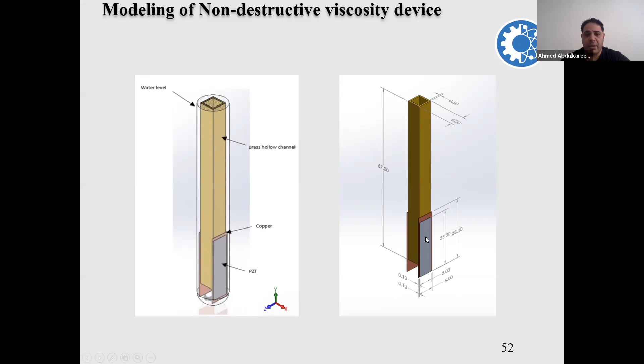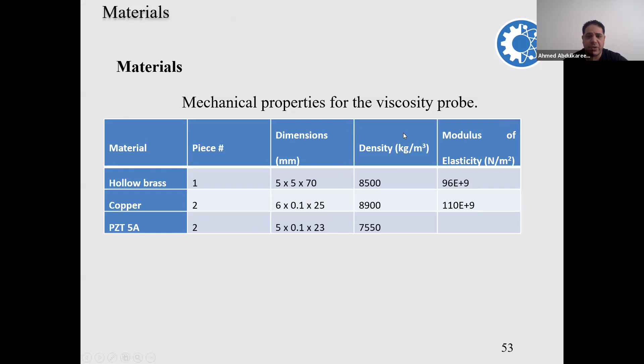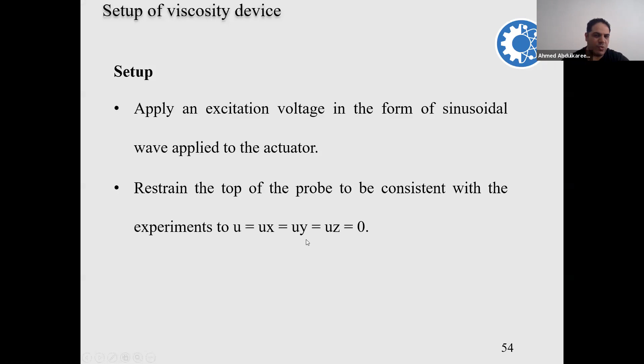So right here we use the probe with the PZT, fully immersed in a fluid. This is the probe with the dimensions. Right here are the mechanical properties for the viscosity probe: the hollow brass, the copper, and the PZT5A. The setup includes applying the excitation voltage, in the form of a sinusoidal wave, to the actuator. We constrain the top of the probe to be consistent with the experiment. The deformation in the X, Y, and Z direction equals 0. The solver includes the modal acoustic analysis, which calculates the mode shapes of vibration for the probe and the surrounding fluid, and the harmonic analysis using the two-way fluid structure interaction, FSI, to find the phase shift for the actuator sensor PZT pair under the excitation of the applied voltage.